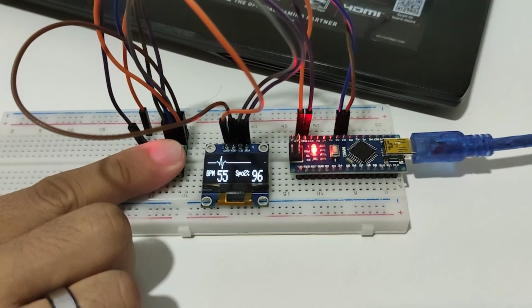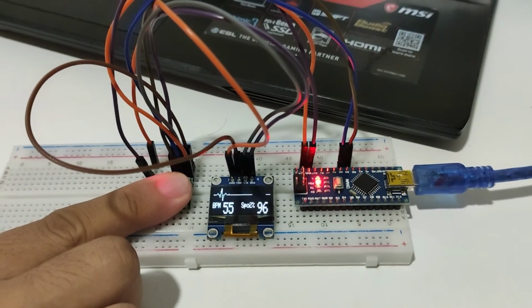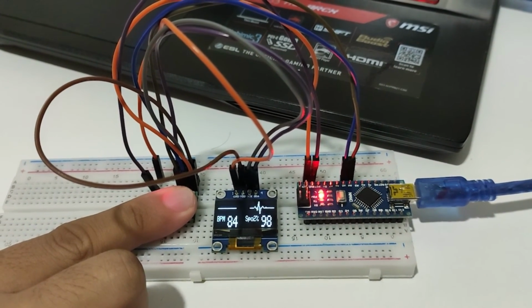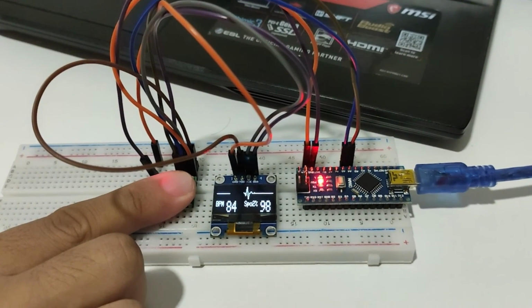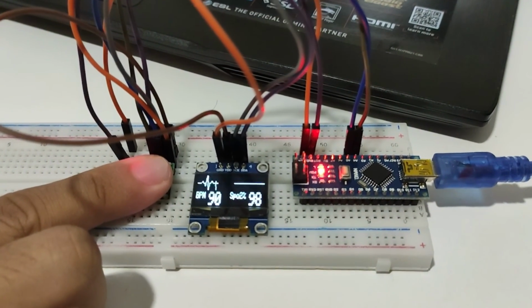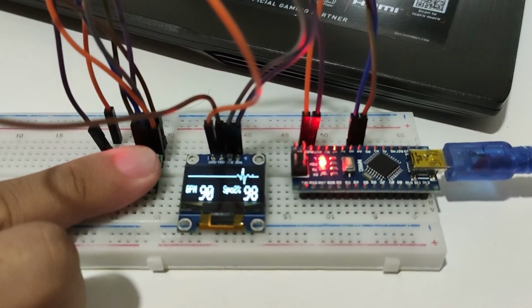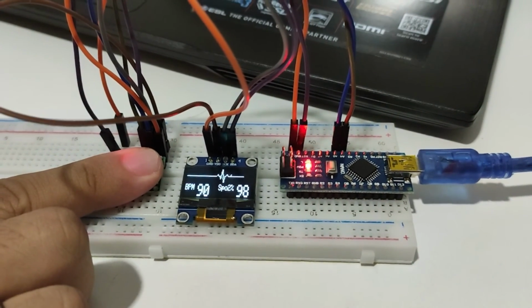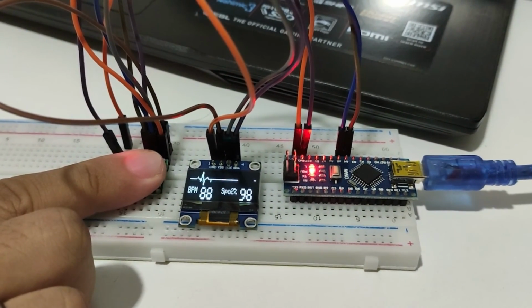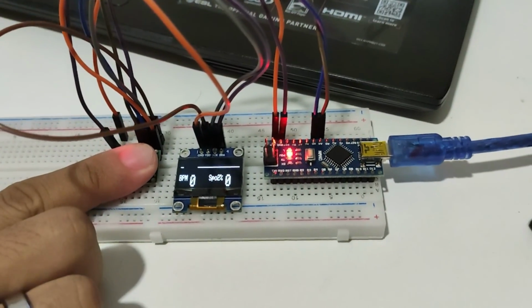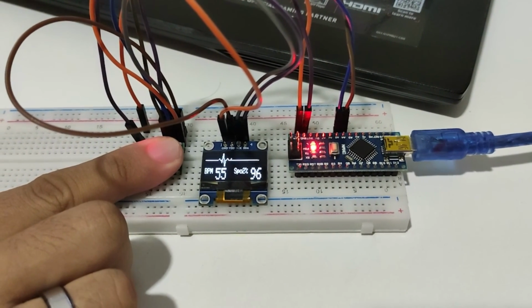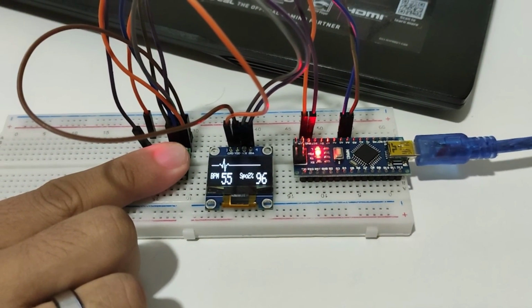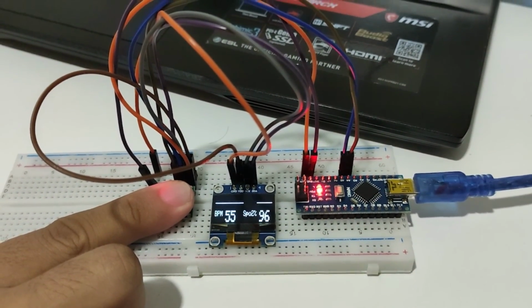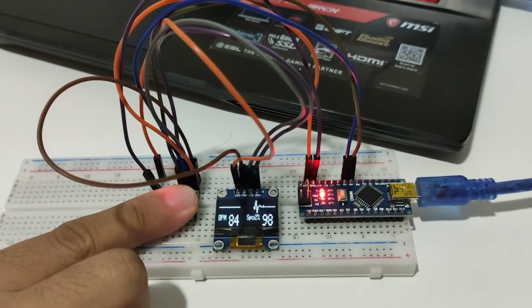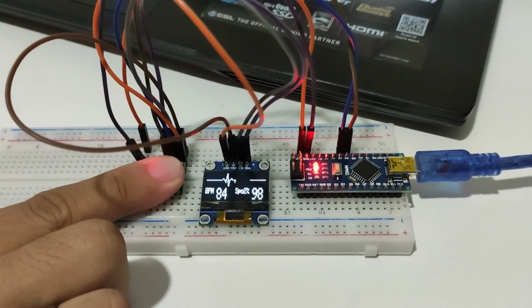So basically, an oximeter has two different kinds of light that are shined through a thin part of a patient's body, such as the finger. The two different lights are red light and infrared light. So the basic working principle behind it is that blood absorbs light differently depending on the level of oxygen it contains. And the oxygenated blood absorbs more infrared light than the red light. So by comparing the changes in the amounts of red and infrared light received, the instrument, the oximeter, can calculate the SpO2 reading.